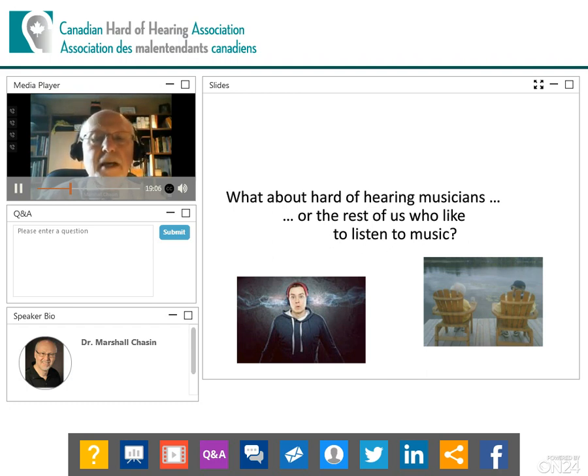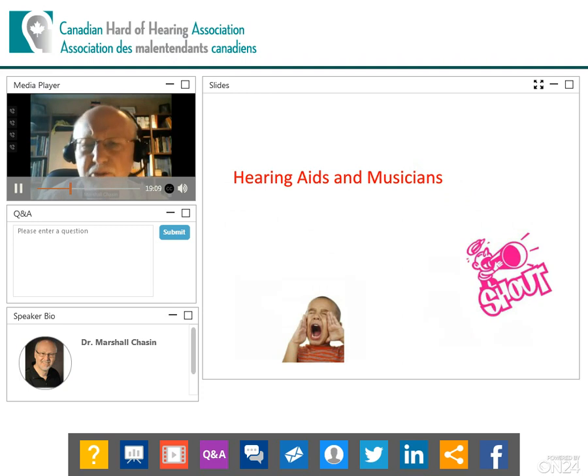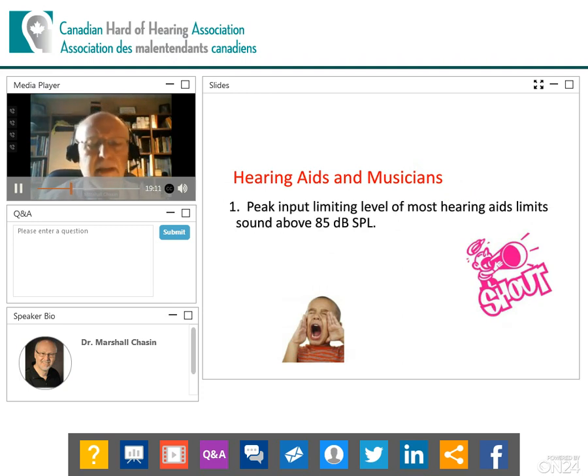Well, let's talk about the first element, which is really very technically sounding, but don't panic. It's not. It's called the peak input limiting level. Think of that as the ceiling or the highest point that can get into the hearing aid. So you have the microphone, then because we're dealing with digital hearing aids, it has an analog to digital converter, an A to D converter, and then it applies it into the hearing aid for it to work with all its magic and its programs that your audiologist will set up for you.